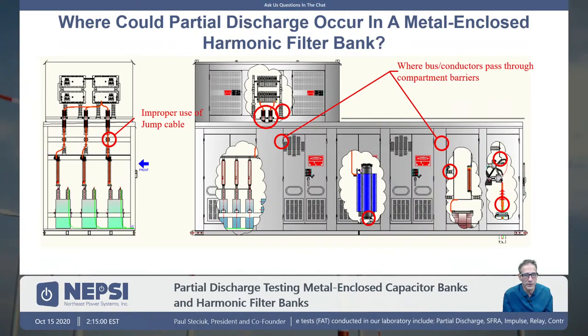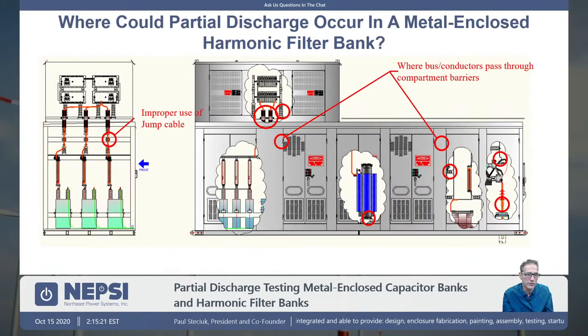So theoretically, there should be no partial discharge there. But if there's a defect within the bushing itself, you would have partial discharge within an air bubble that might be inside that bushing. So this partial discharge testing is important to detect defects in the manufacturing process that might occur. You can get it along all the insulators within the equipment. So across all your equipment, you have insulators, and you're going to get tracking along the outside that will show up as partial discharge.